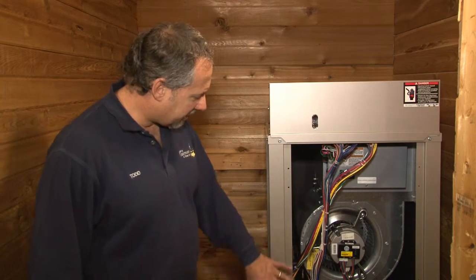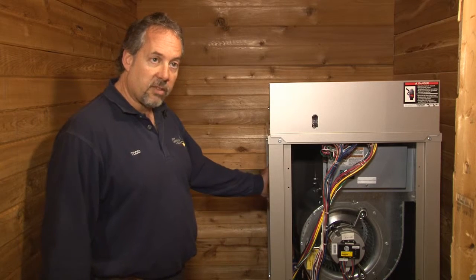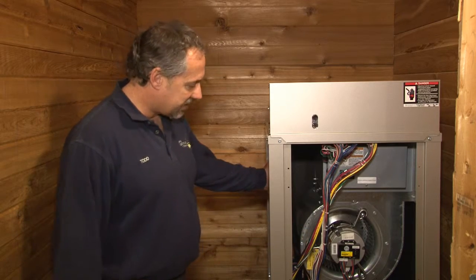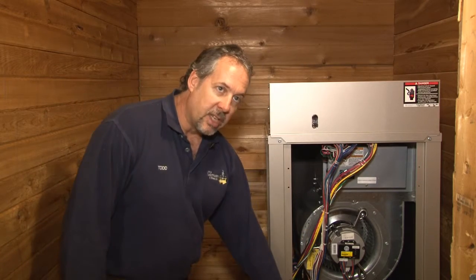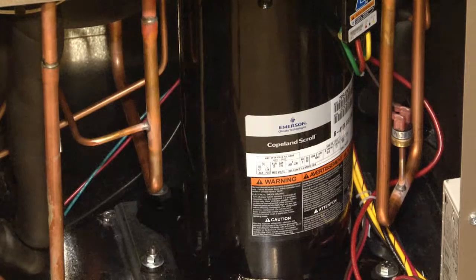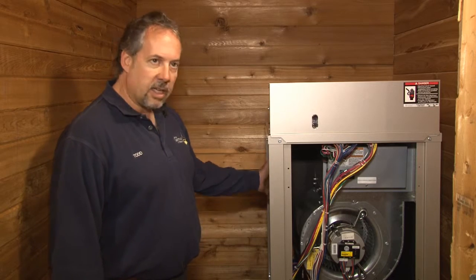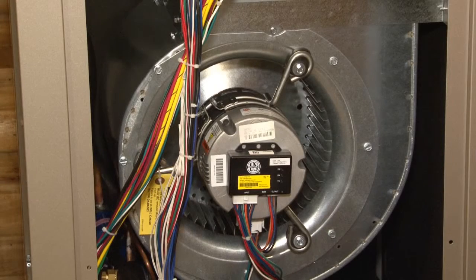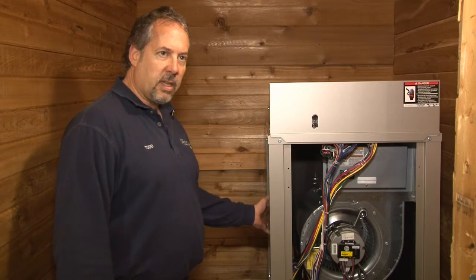This is basically an air conditioning unit that has the condensing coil on the side here, similar to a typical outside condensing unit, but it's built in inside. Behind the unit is the heat exchanging unit that exchanges the heat from the outside coils. You can see the compressor that compresses the refrigerant, runs it through the coax heat exchanger, and then through the condensing coil. Our variable speed blower takes the return air, runs it across that coil, heats up the air, and blows it out through the ductwork we'll be installing later on.